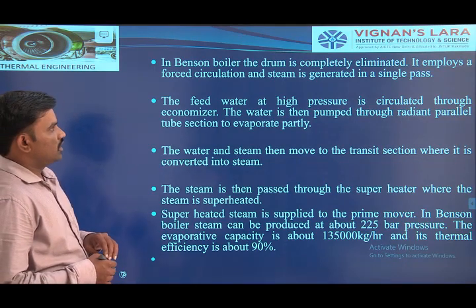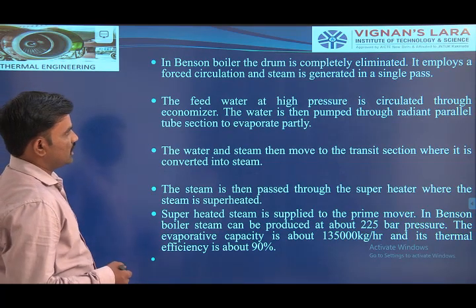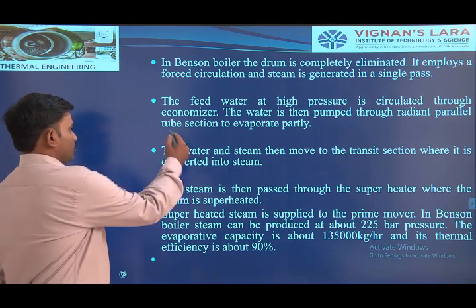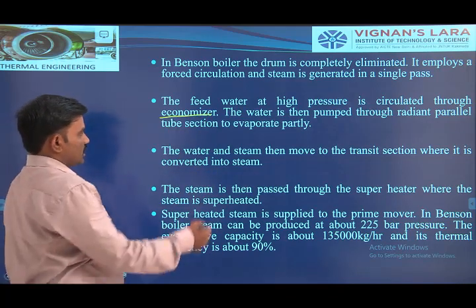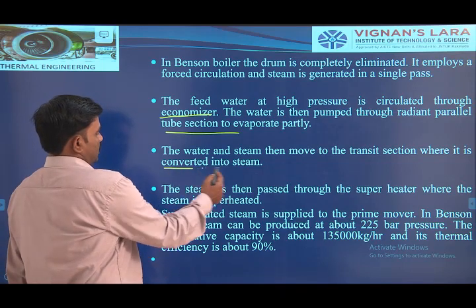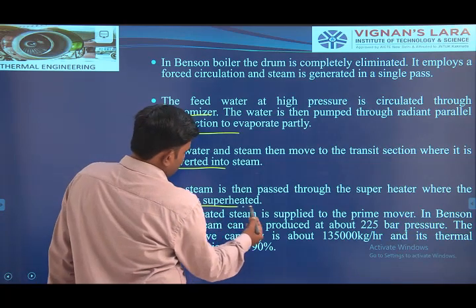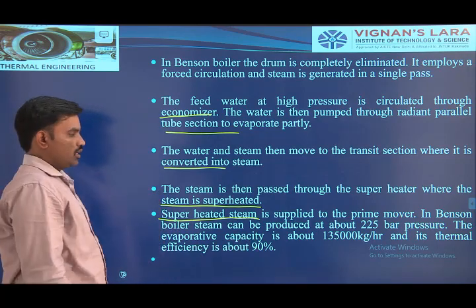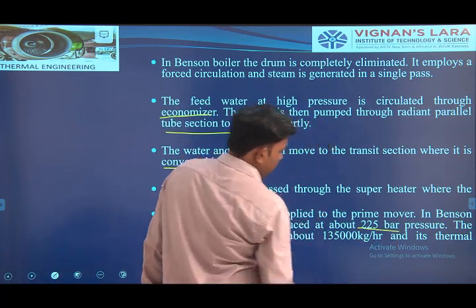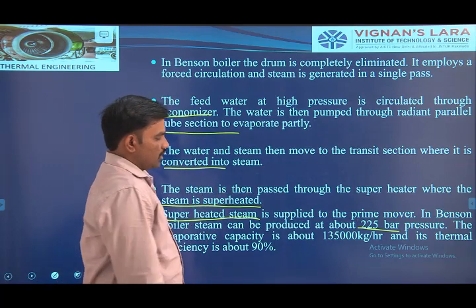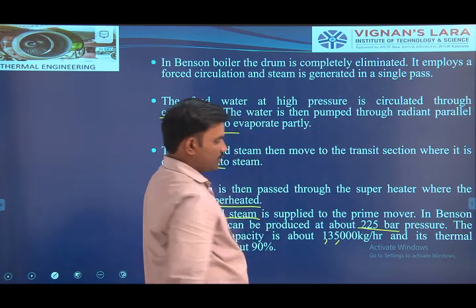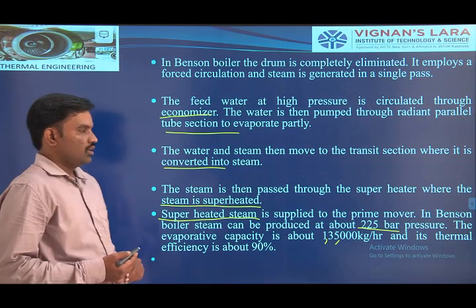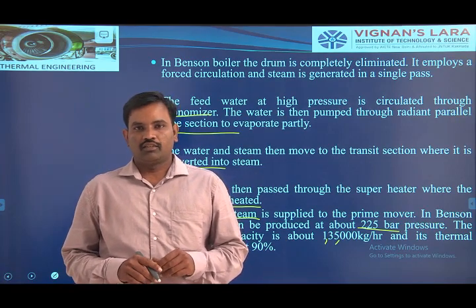The Benson boiler has no drum — it is completely eliminated. It employs forced circulation, and steam is generated in a single pass. Feed water at high pressure is circulated through the economizer; hot water is sent to the radiant evaporator tubes and converted into steam. The generated steam is heated in the superheater section and converted into superheated steam. That superheated steam is introduced into the prime mover, and from the prime mover we are producing work output. The generated steam pressure is 225 bar, and this type of boiler is used to generate 35,000 kilograms of steam per hour. These are the different types of boilers we are using in steam power plants. Thank you.